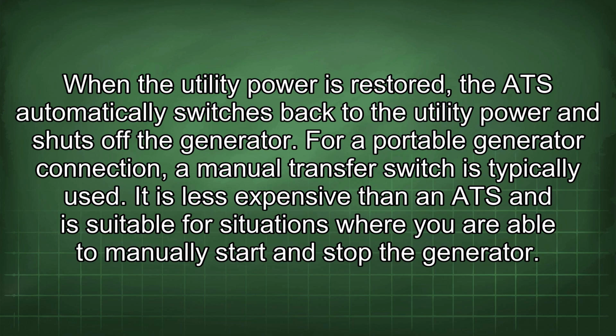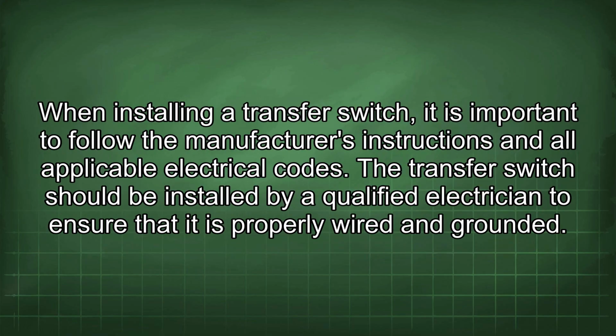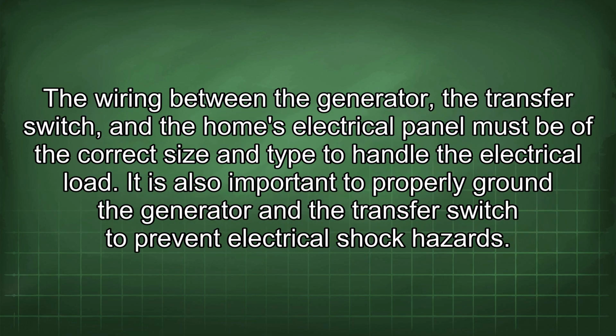It is less expensive than an ATS and is suitable for situations where you are able to manually start and stop the generator. When installing a transfer switch, it is important to follow the manufacturer's instructions and all applicable electrical codes. The transfer switch should be installed by a qualified electrician to ensure that it is properly wired and grounded. The wiring between the generator, the transfer switch, and the home's electrical panel must be of the correct size and type to handle the electrical load.